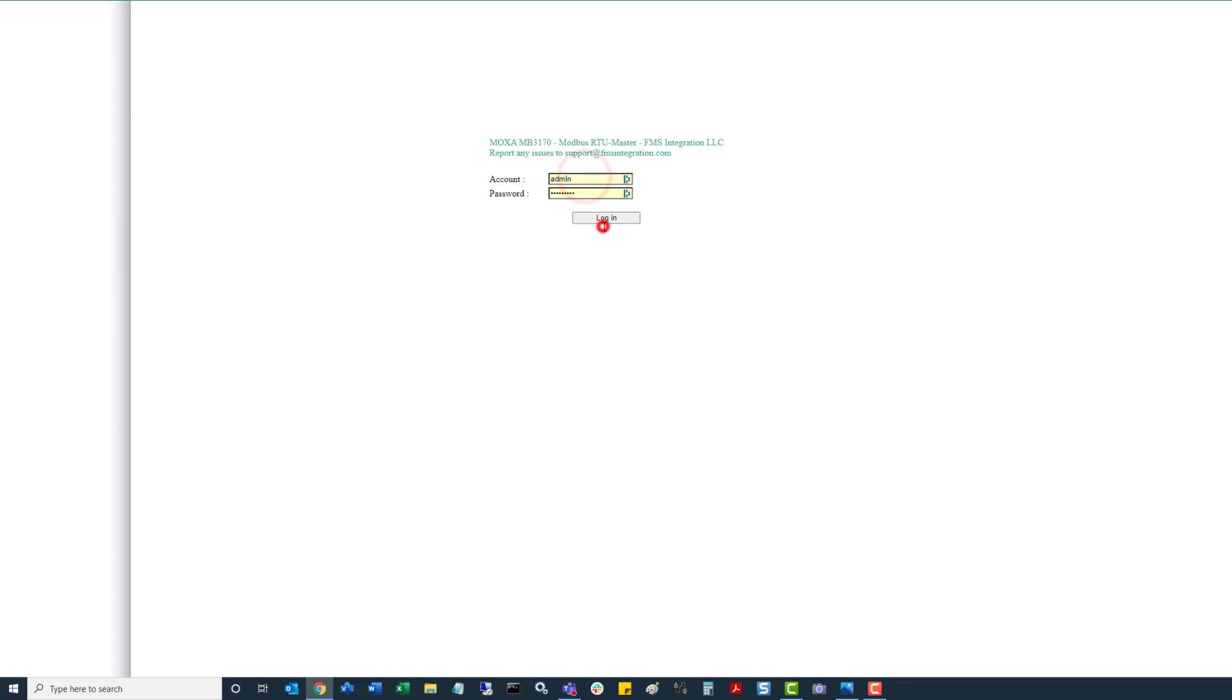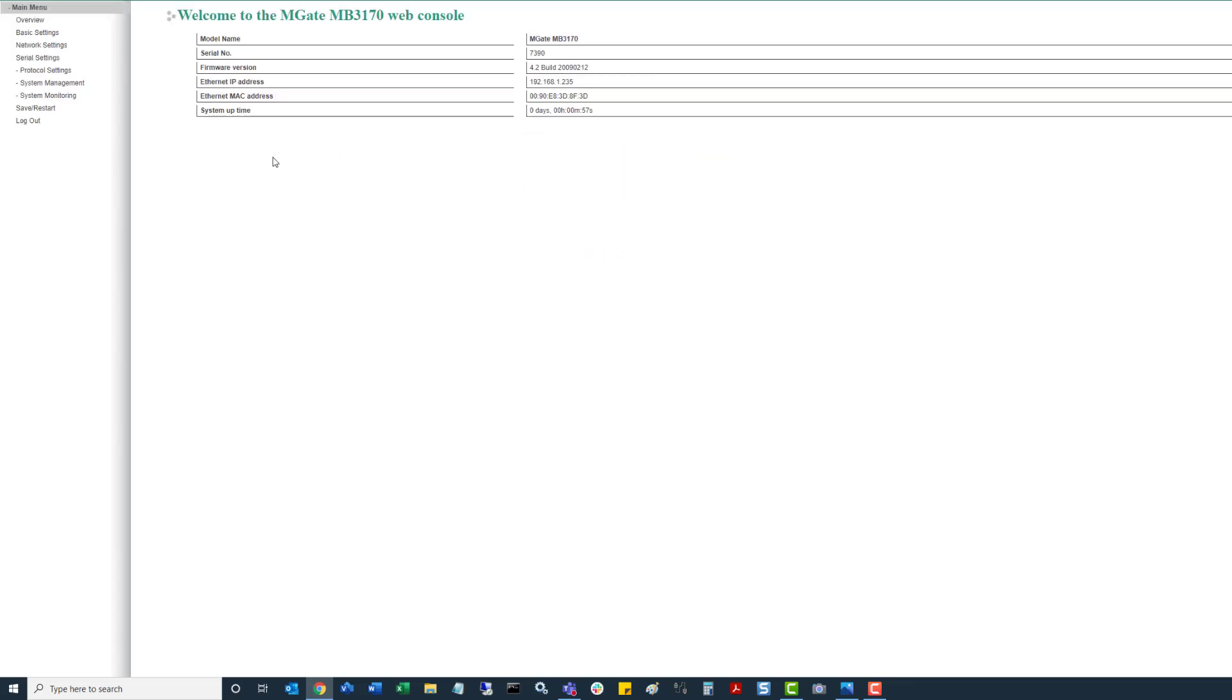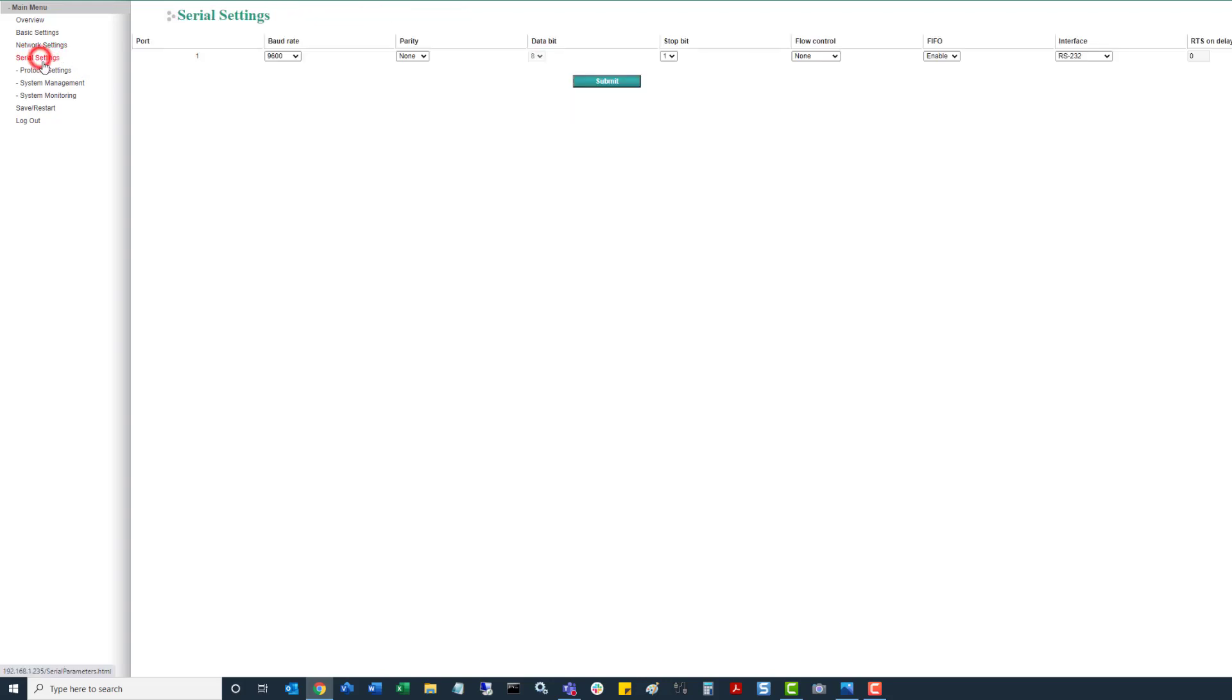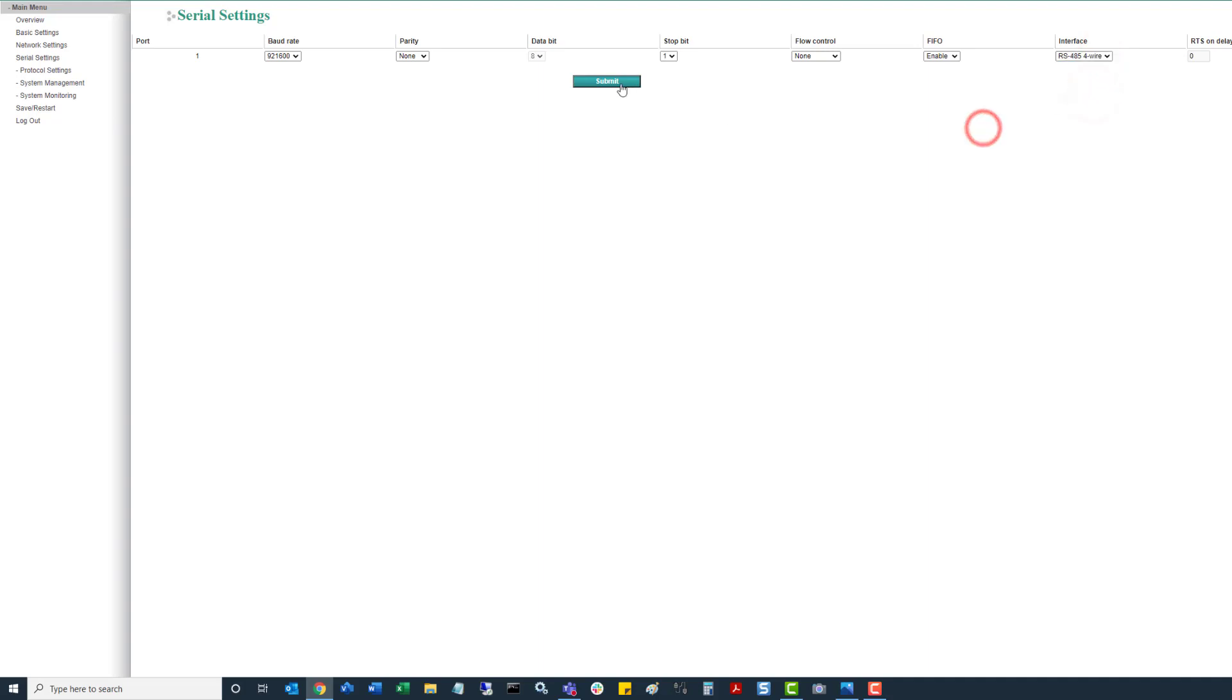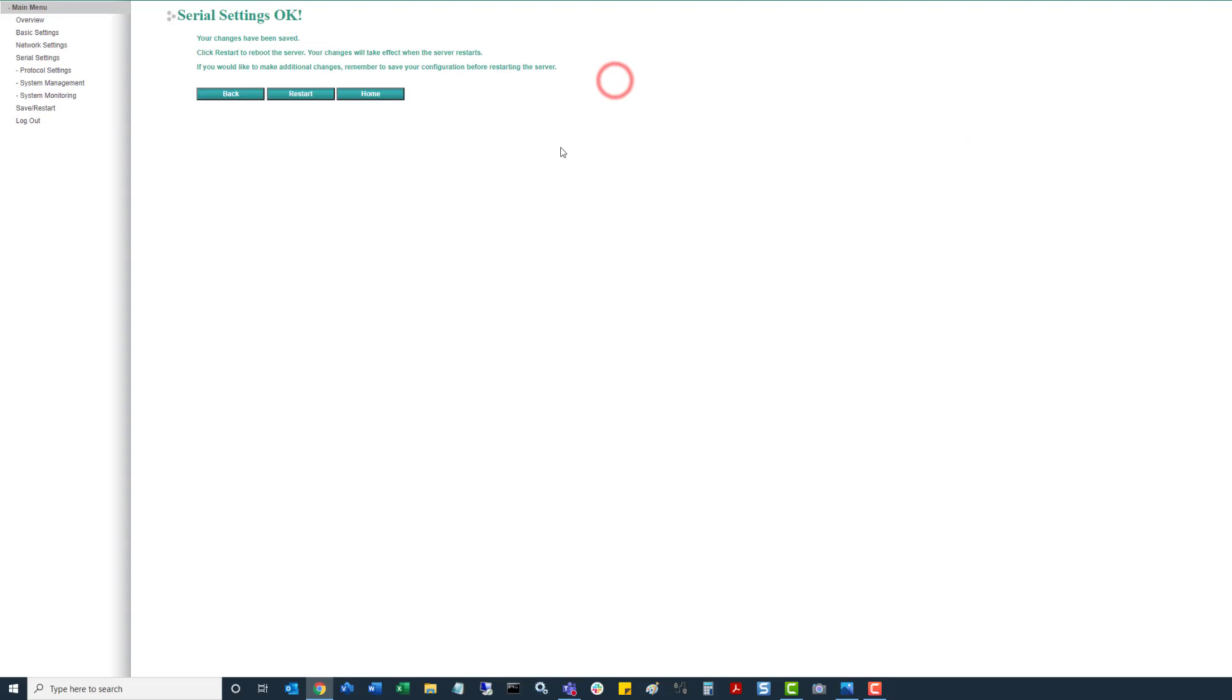So first thing we want to do is log into the unit, go to home. First you want to optimize the serial setting so left click on that, and then we want to change it to the max speed 921600. We leave parity at none, data bit at 8, stop bit at 1, flow control to none, first in first out enabled, and then change the interface from RS232 to RS485 4 wire. Click on submit.